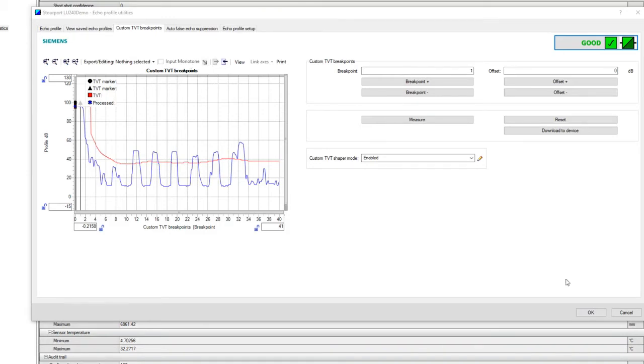So remember what we said, the echoes are scored above the red line, and they're done on height, area, and whether they're first, second, or third, or last. So what we have to do is increase the score of the true echo, which is this last one, and decrease the score of these, because at the moment the overall score is shared amongst these.